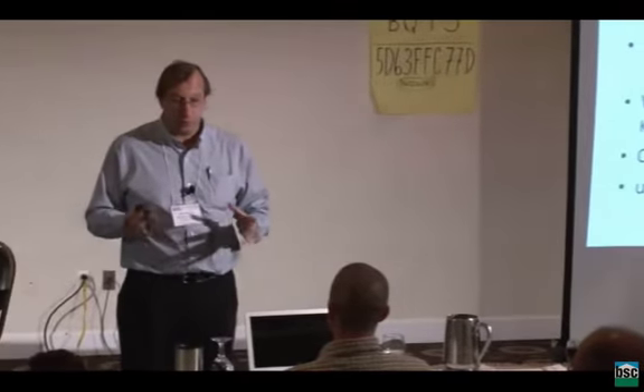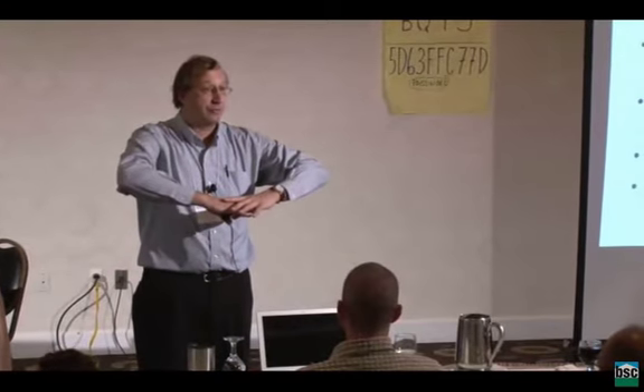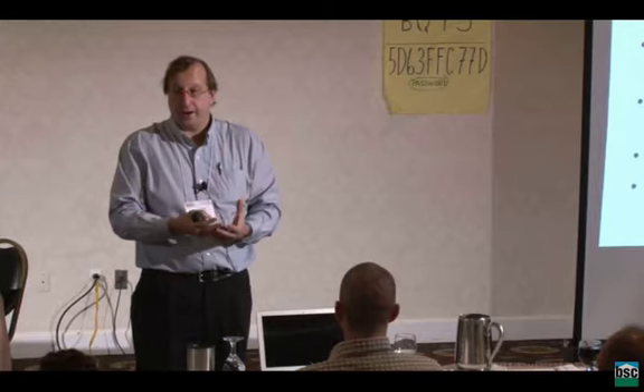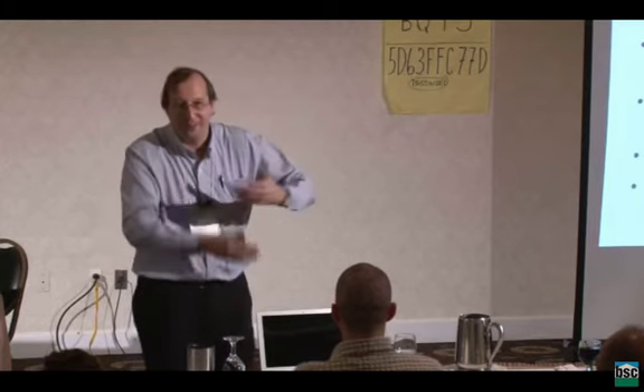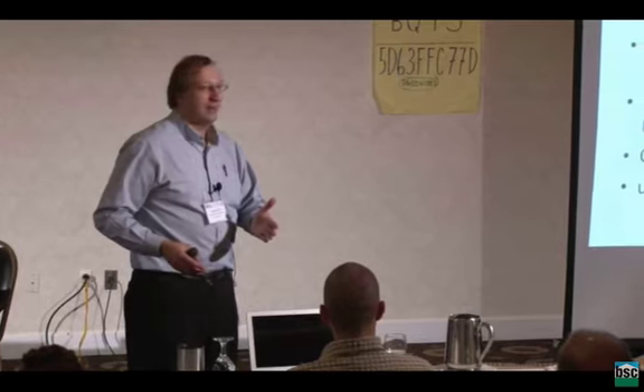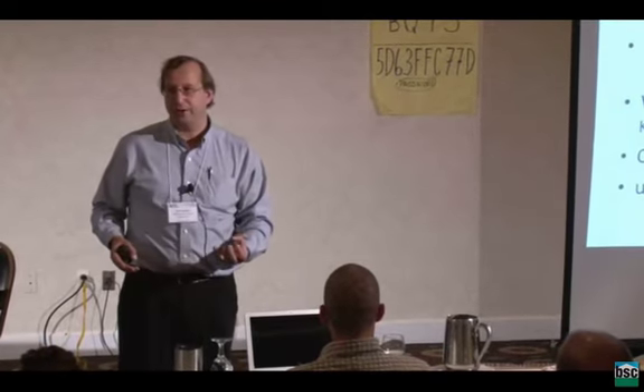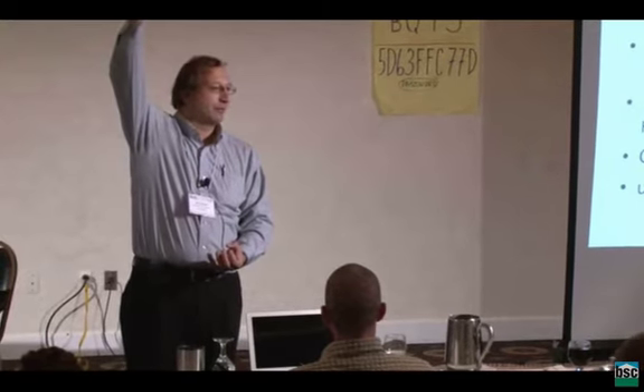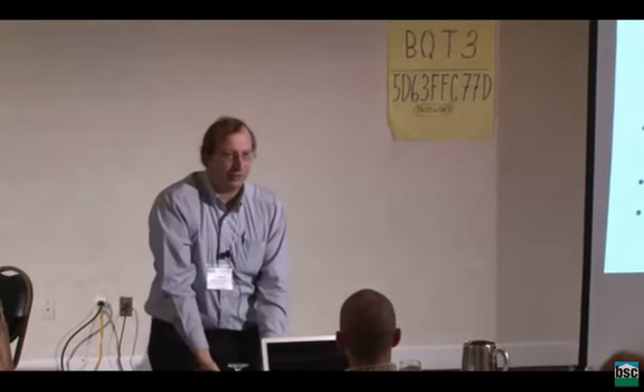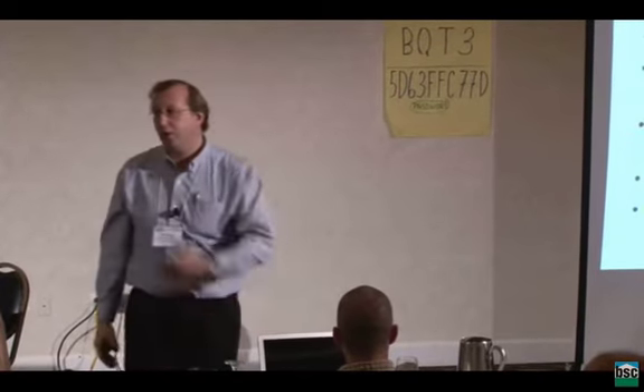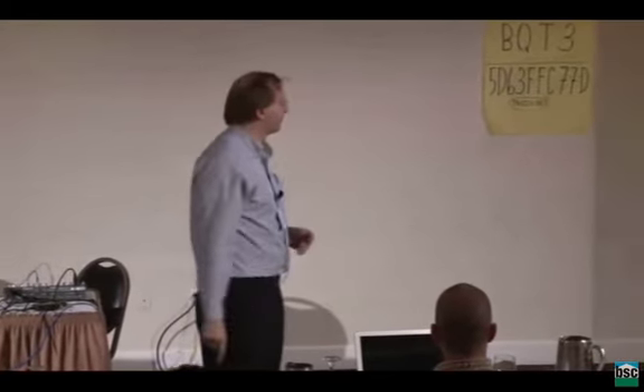Originally, they tried to not install air conditioning on the 2nd floor. And in the wintertime, it worked fine. They had a central heat source in the middle of the 1st floor, and the air would get hot, and it would rise, and cold air would fall, and we'll talk about that in a bit. So the hot air would rise, and so the temperatures in the upper floors were actually okay. But come the 1st summer, the reverse doesn't work. So they're blowing cold air around in the ground floor, and that didn't get to the 2nd floor, because of course the cold air wants to stay on the 1st floor. And so they now install air conditioning units on the 2nd floor in all their models to avoid any potential of comfort complaints.